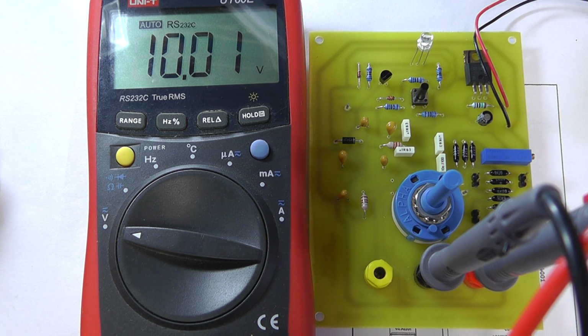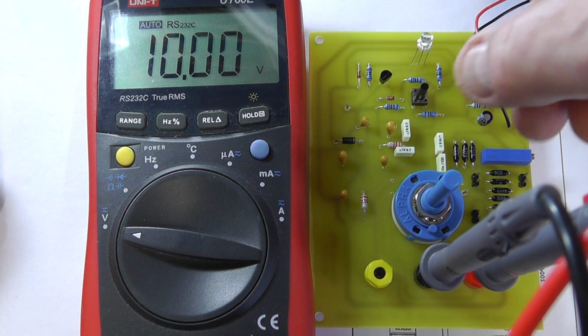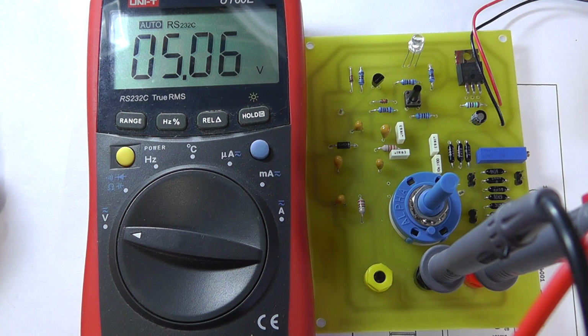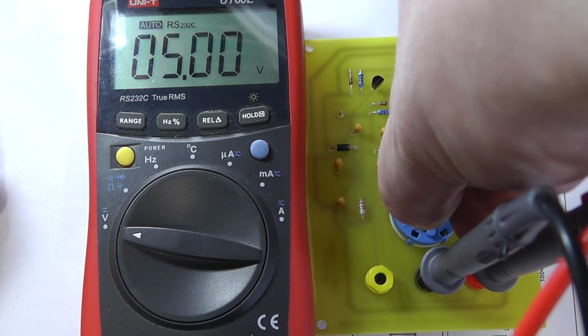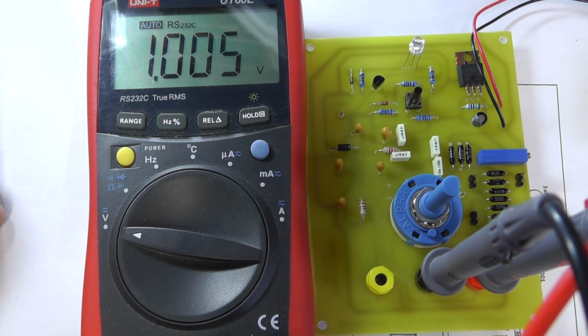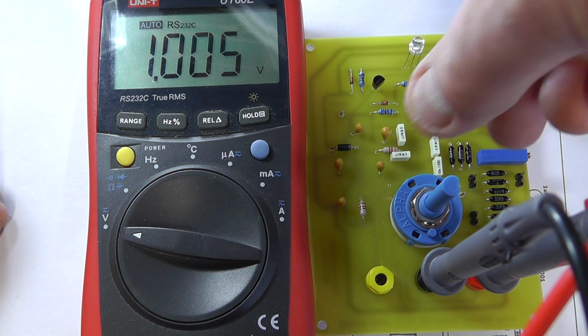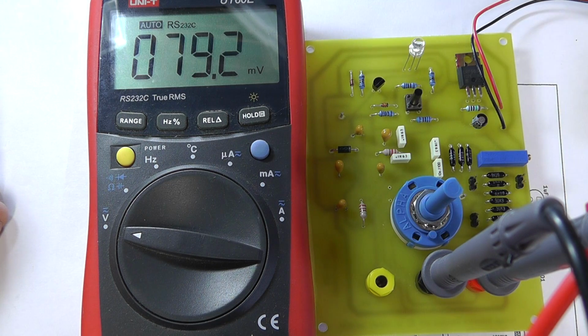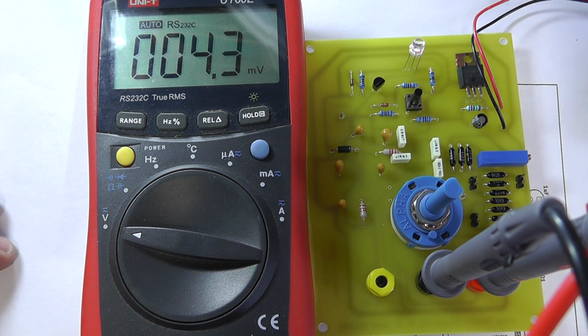It's switched at the moment to the 10 volt range. That's what it's reading, 10 volts. I'll switch it now to the 5 volt range. 5 volts. Go to the 1 volt range. The 1 volt range there is slightly out of calibration, but we'll come back and calibrate the unit. Let's just go to the 100 millivolt range. It's just a fraction over 100 millivolts, so again that needs calibrating. But the unit seems to be working fine, so I think the next thing is to calibrate the unit. It's powered itself down now.